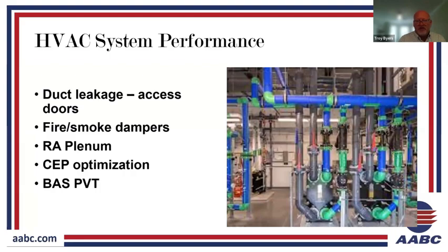Again, damper alignment comes into play with smoke dampers, to make sure that the damper is fully shutting and fully opening and aligned with its actuator. Return air plenums, where we have plenum air return going back to maybe an air handler that's located centrally on an office building floor. All of the return air goes above the ceiling through the plenum and travels back to that central location. So we want to observe any blockage, like fire dampers in rated walls that might be closed and preventing that return air path back to the unit. Also, the return air path or transfer air path in conditioned spaces, to make sure we have a transfer grille, for example, in each office space or each enclosed space, to get that return air back to the unit efficiently and with the least amount of pressure drop.